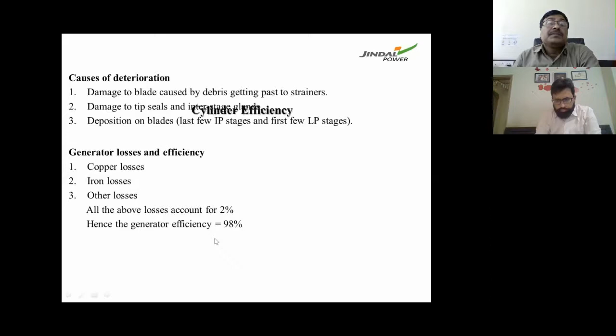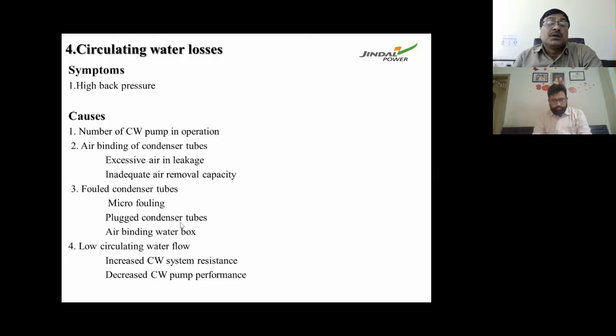Circulating water losses are there, like the CW water for the condenser. It is due to high back pressure, which amounts to a lot of kilocalorie loss. The causes may be that a sufficient number of CW pumps are not in operation, air binding of condenser tubes, excessive air in-leakage, inadequate air removal capacity, fouled condenser tubes, microfouling, and plugged condenser tubes. These are to be regularly monitored in every plant to improve the heat rate and save the financial impact.